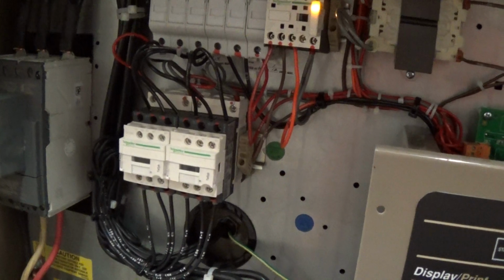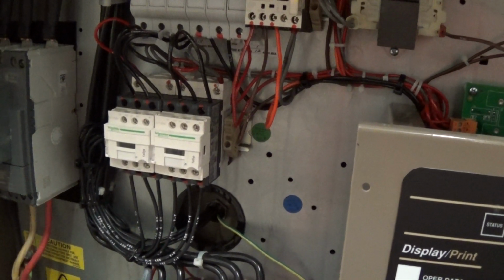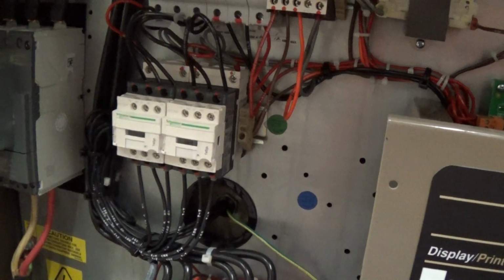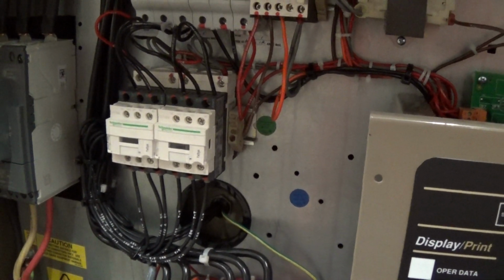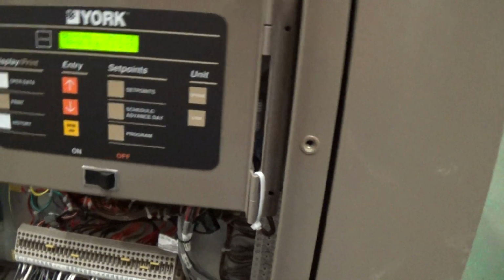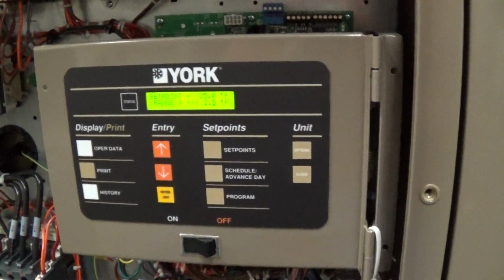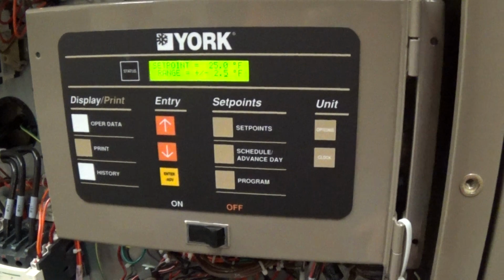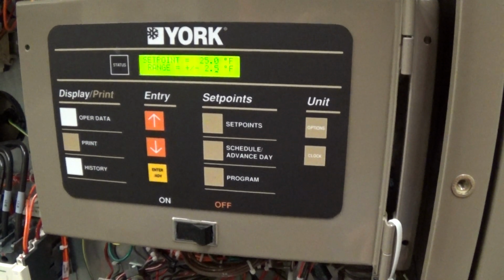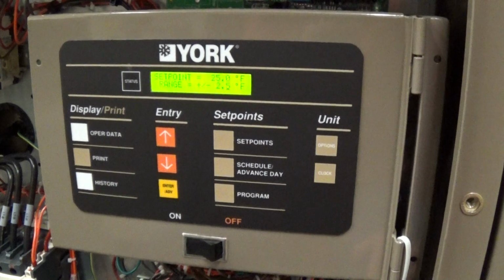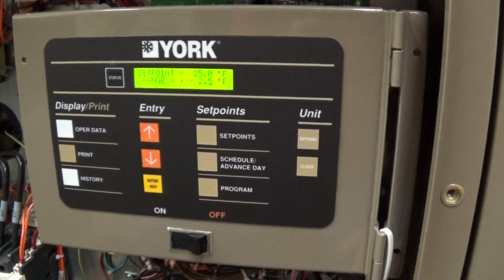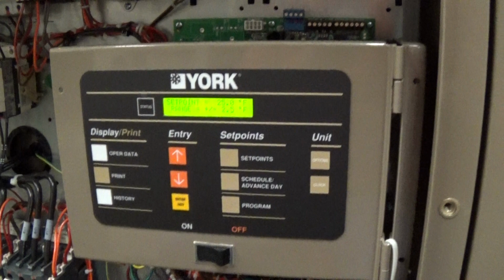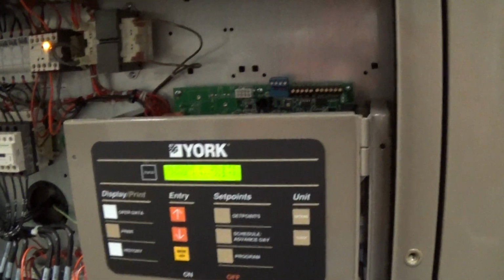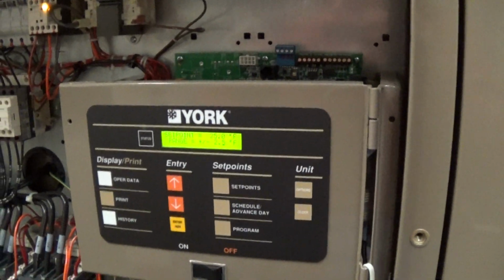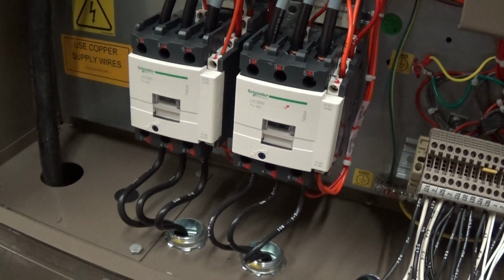Even though we have a variable frequency drive on one of the condenser fans, we still have two contactors here for each fan. A lot of the cutouts and the options for the low and high pressures and the low and high ambient, we already have kind of preset here because we're doing this runoff for this video and the demo for a customer. But all the new York chillers we sell with the York startup assistance. And you can just hear the second compressor just kicked on there.